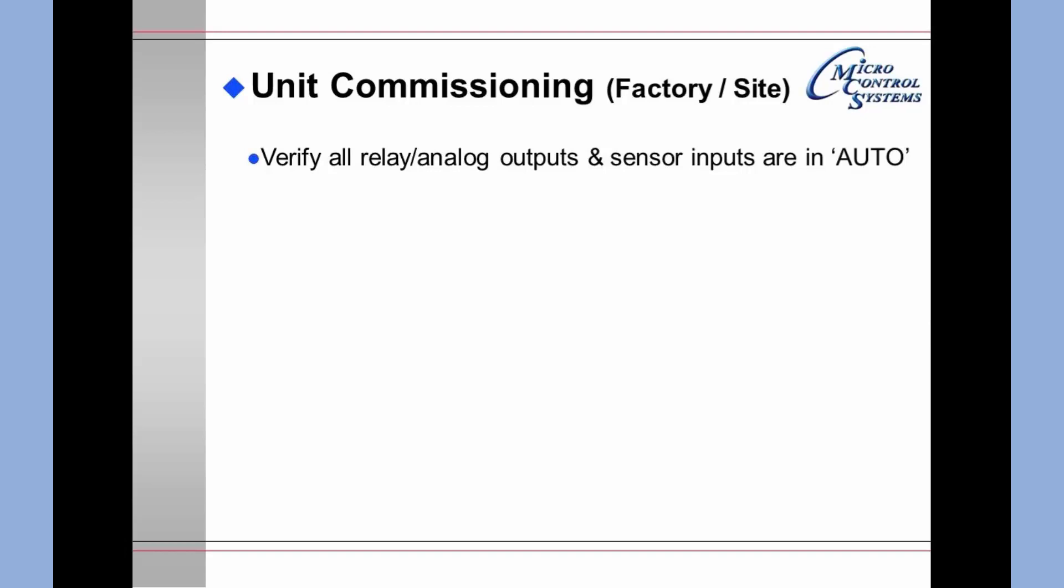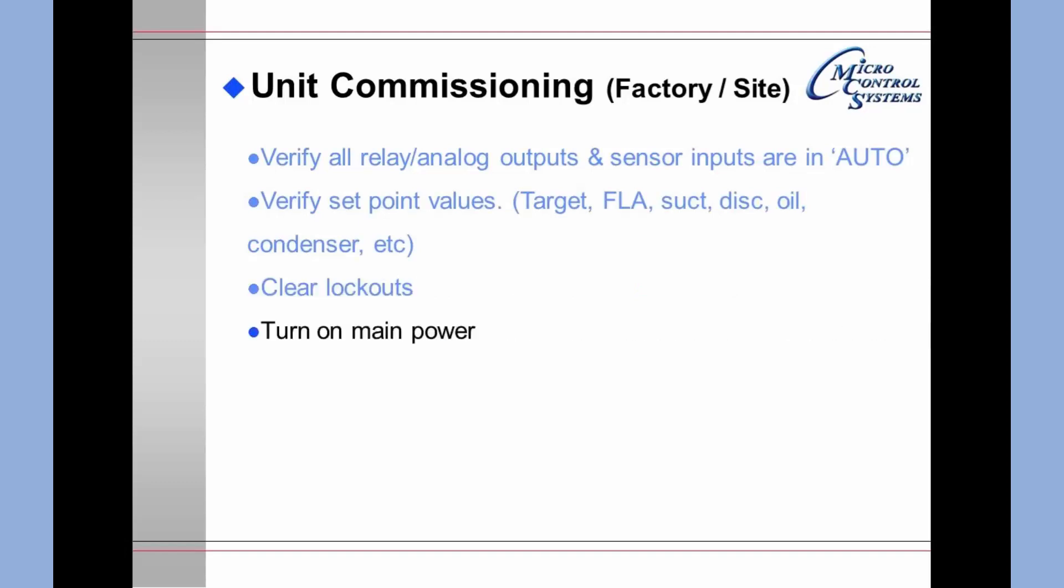Verify all relay and analog outputs and sensor inputs are now in auto. Verify the set point values. You should review the target, the full load amps, the suction, the discharge, the oil, and the condenser set points, that they all look reasonable. Then you should clear the lockouts and turn on the main power.